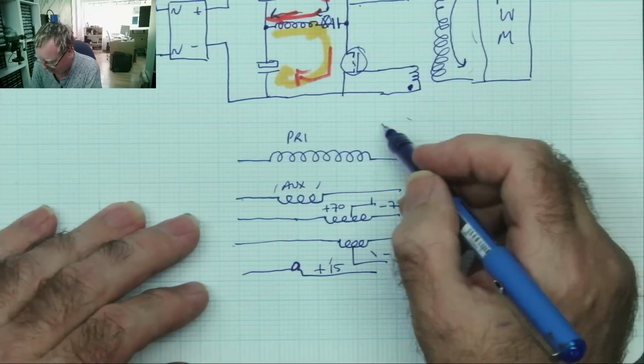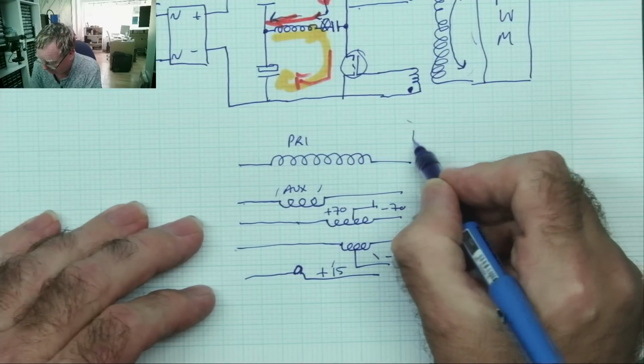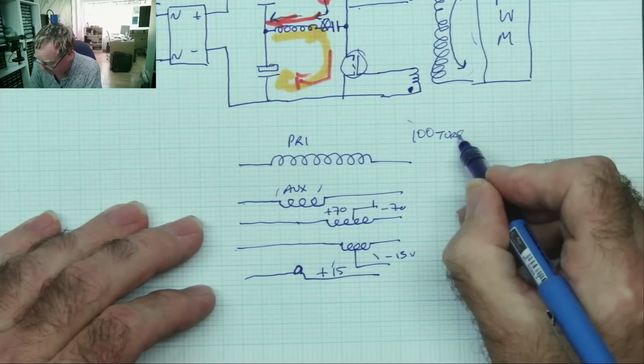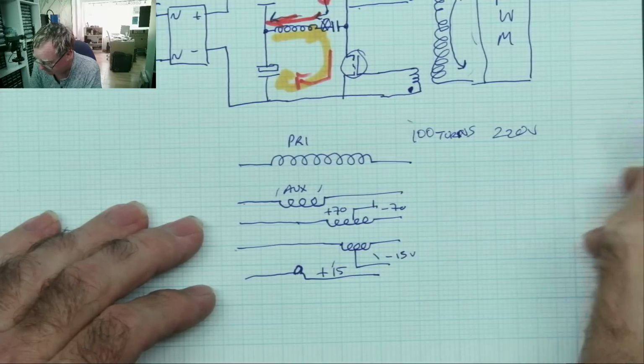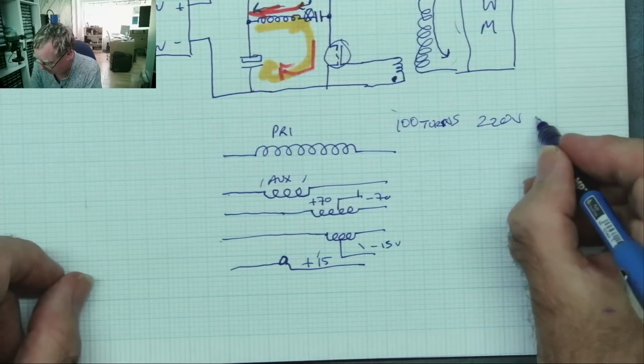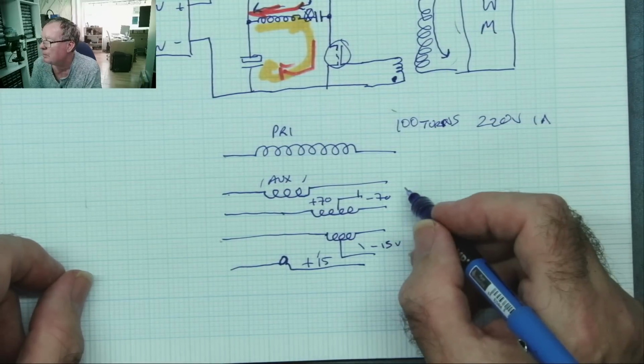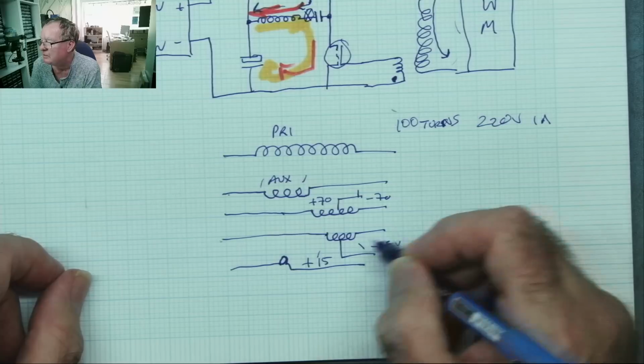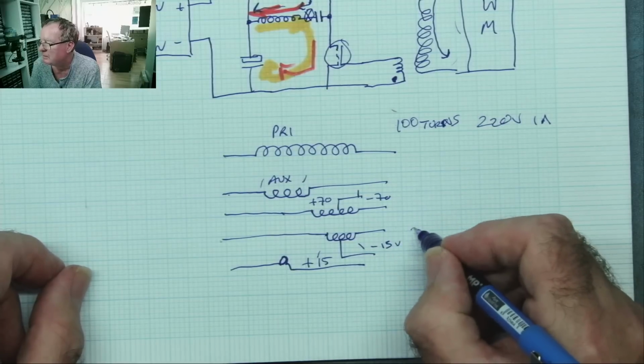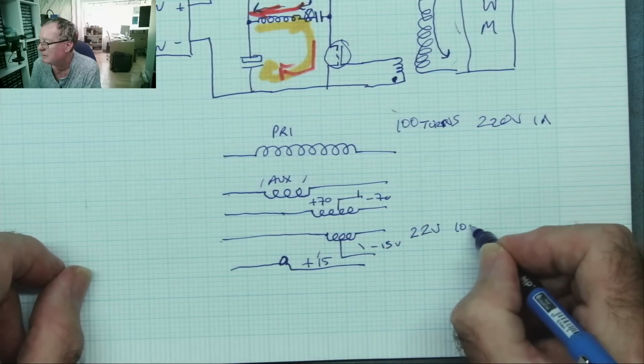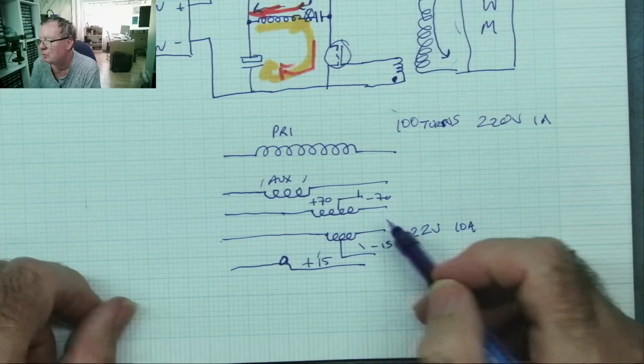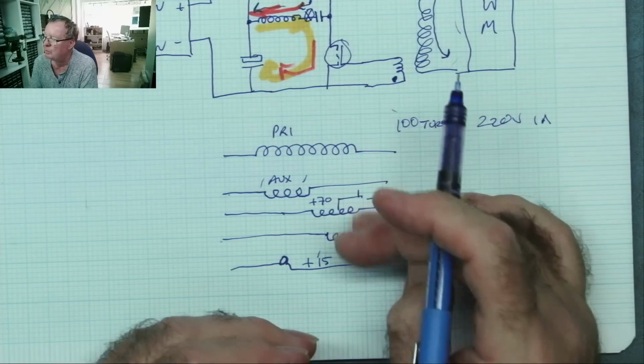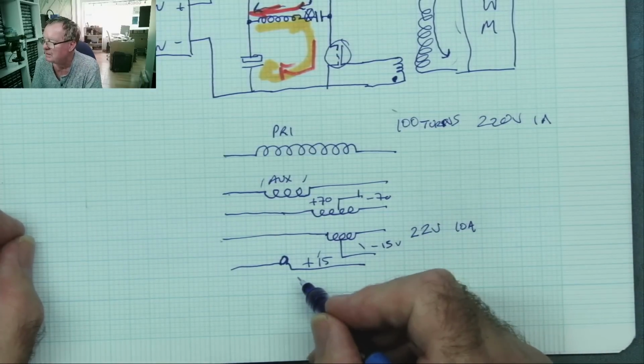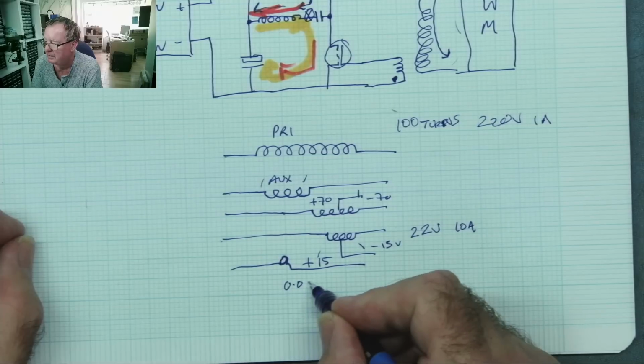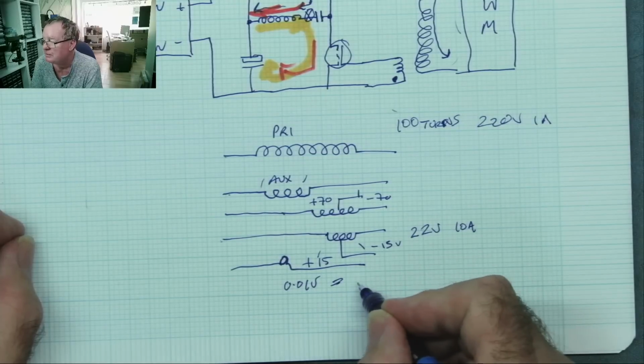You know how this works. If the primary has, for example, 100 turns at 220 volts, 1 amp, and an output winding was 22 volts, that would be able to give us 22 volts at 10 amps - a tenth of the voltage, 10 times the current. Obviously the maximum of all the windings added together will have a limit, but that's basically how it works. And this shorted winding is like probably 0 point whatever volts at a very high current.